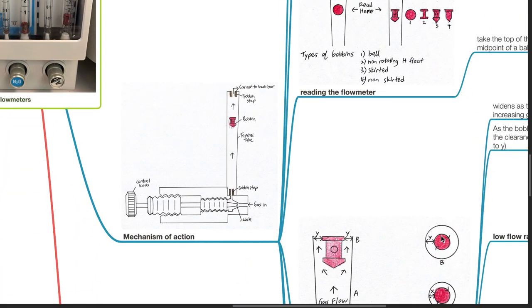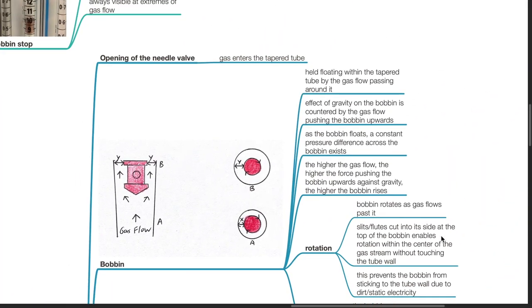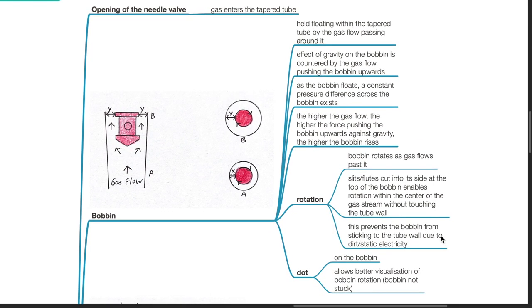Mechanism of action: Opening of the needle valve results in gas entering the tapered tube. The bobbin is held floating within the tapered tube by the gas flow passing around it. The effect of gravity on the bobbin is countered by the gas flow pushing the bobbin upwards as the bobbin floats, a constant pressure difference across the bobbin exists. The higher the gas flow, the higher the force pushing the bobbin upwards against gravity and the higher the bobbin rises.